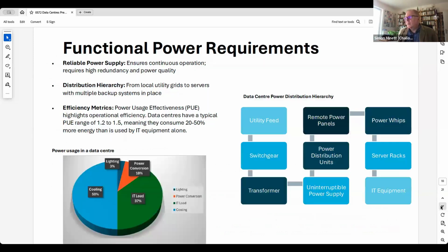I thought it'd be useful, before talking about energy efficiency and grids, to look at where energy goes in a data center. It varies depending on the data center, but around 50% of all electricity going in is used for cooling, a little bit for lighting, a little bit for power conversion, and about 38% is for the IT load. So significant ancillary loads compared to its actual function, which is IT - and cooling is by far the largest of those issues.